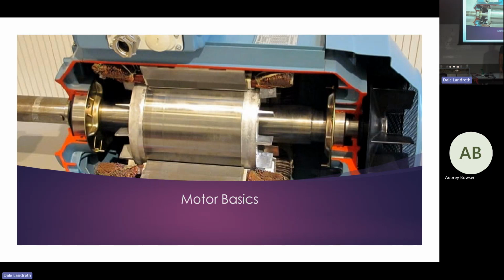2.2 giga ohms at 1,000 volts, meaning no continuity to ground or between windings. That's basically like looking at our meter and seeing OL, infinity. So there's nothing going between the windings and the casing or motor housing, or between the windings themselves. That insulation is perfectly sealed, for lack of a better term.